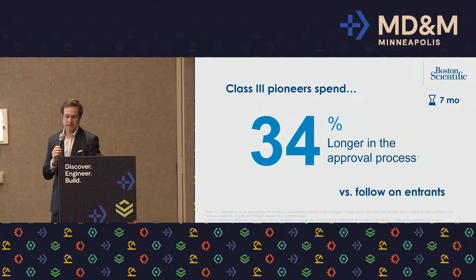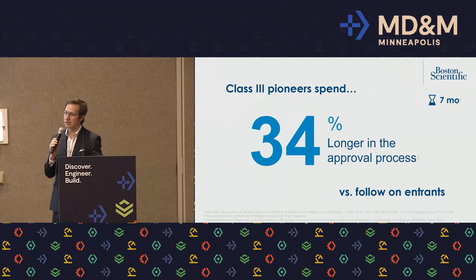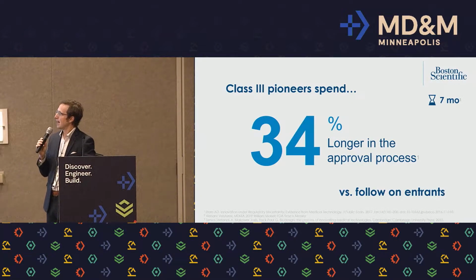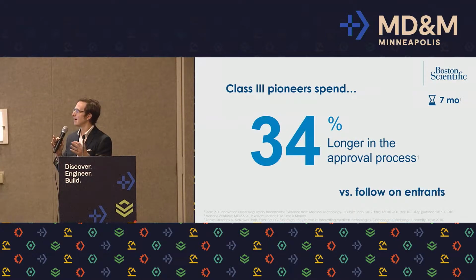So I can't stress enough the importance of talking with FDA early enough. There was a paper published a few years ago by Ariel Stern and others at Harvard Business School that conducted an analysis over the last 10 years, including Class 3 products that have been approved through FDA. And what they found was that sponsors of Class 3 medical devices spend about 34% longer in the approval process versus follow-on entrants if they're the first in a product code.